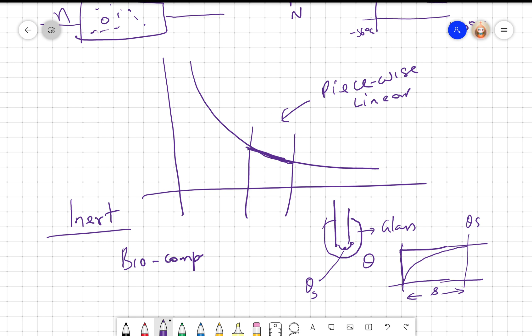So whenever you want a biocompatible temperature measurement in a small range, you can use a thermistor - not because they aren't useful for large ranges, but they're not as popular there. You can linearize the exponentially decreasing characteristic.